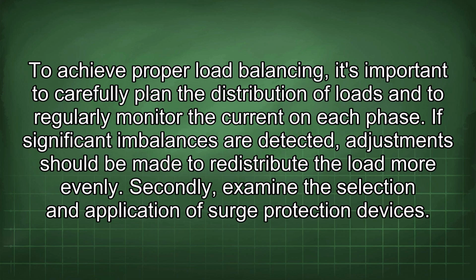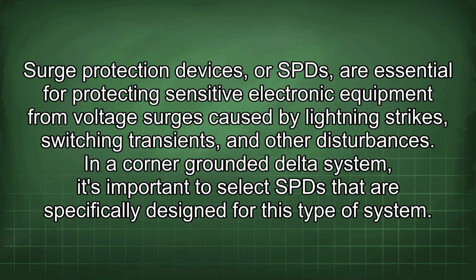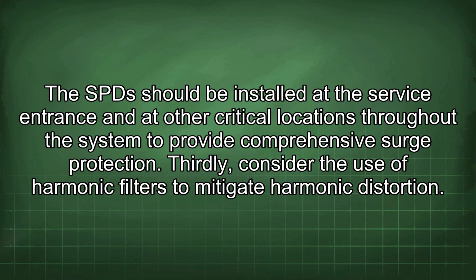Secondly, examine the selection and application of surge protection devices. Surge protection devices, or SPDs, are essential for protecting sensitive electronic equipment from voltage surges caused by lightning strikes, switching transients, and other disturbances. In a corner-grounded delta system, it's important to select SPDs that are specifically designed for this type of system. The SPDs should be installed at the service entrance and at other critical locations throughout the system to provide comprehensive surge protection.